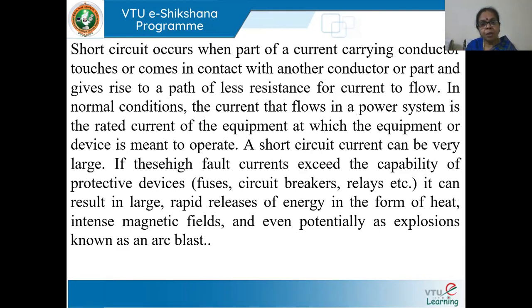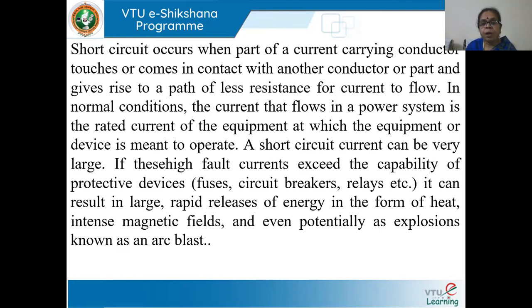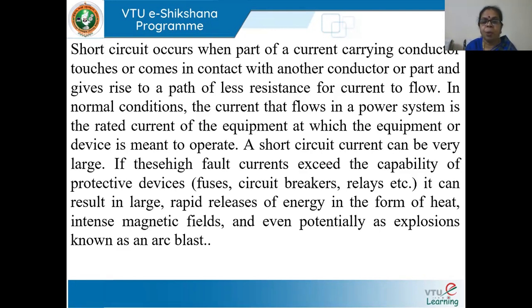As compared to normal currents, a short circuit current can be really, really large. If you look at your protective equipment like circuit breakers, they will have some finite time for action. So in this short duration the short circuit current will flow, and for a very short duration after the short circuit, it's possible that your devices and components of the network will be carrying very high currents. By high currents I'm not talking of 10% or 20% more than the normal value — we are talking of 500%, 600%, so in terms of per unit it could be five per unit, six per unit, sometimes as high as 10 to 12 per unit.